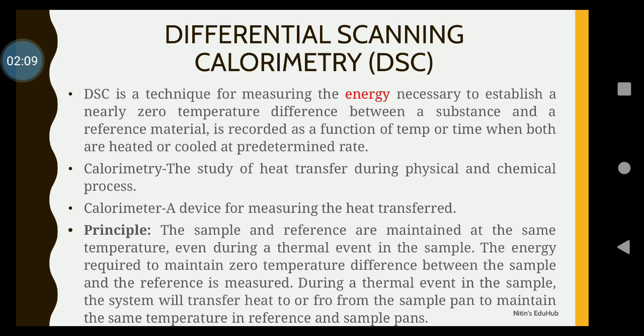The principle is based on the sample and the reference being maintained at the same temperature. Even during a thermal event in the sample, the energy required to maintain zero temperature difference between the sample and the reference is measured. During a thermal event, the system will transfer heat to or from the sample pan to maintain the same temperature in the reference and sample pans.